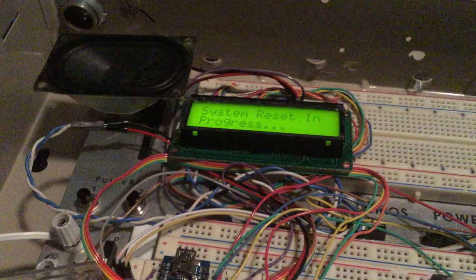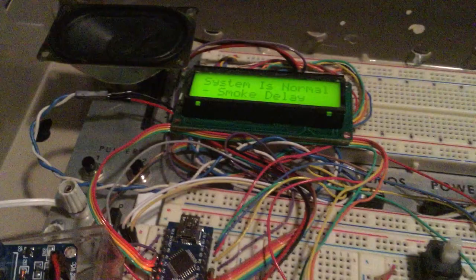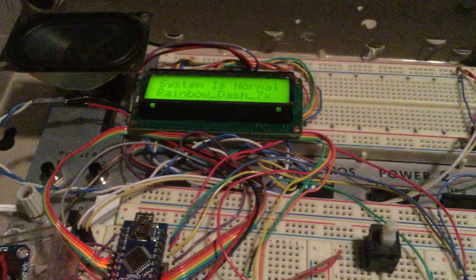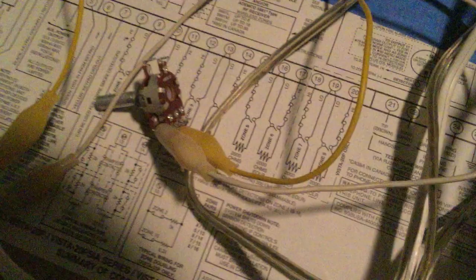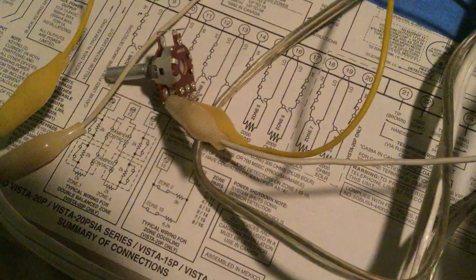So now zone 1 alarm primary remains. So I didn't completely copy the Simplex 4010 as you can tell, but I'll show you what I'm going to change about this that I haven't really seen on many panels except the Simplex 4010. So now let me demonstrate something. Previously, on one of my other videos, when I showed it go into trouble, I had to reset it. Because if the zone was in trouble, it would not go into alarm if you put the zone into alarm. But now, let's put it in trouble real quick.